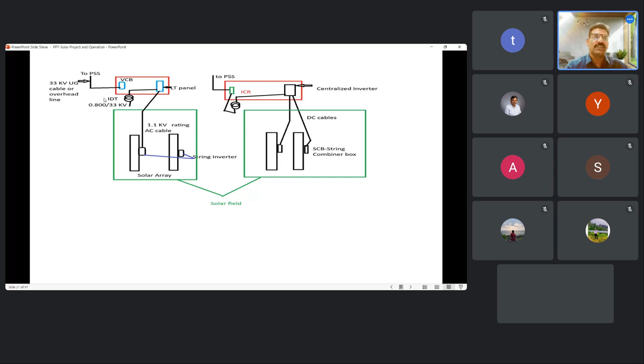So the string combiner box collects DC cables, which go to the IDT, the inverter duty transformer, then to the VCB, vacuum circuit breaker, and through the 33 kV cable it goes to the collection substation. Different ICRs may be 12, 16, or 18 megawatt each, based on the design. This is underground cable, with no pole line. These are the IDT, 800 V by 33 kV.